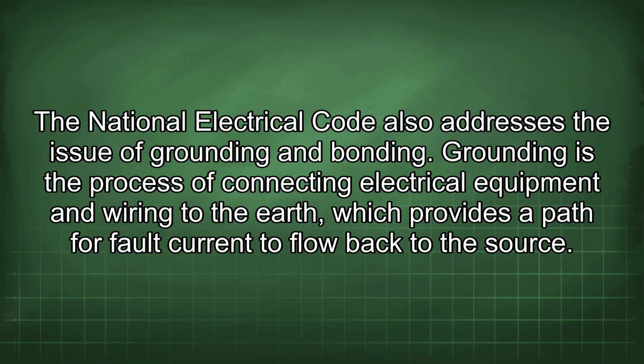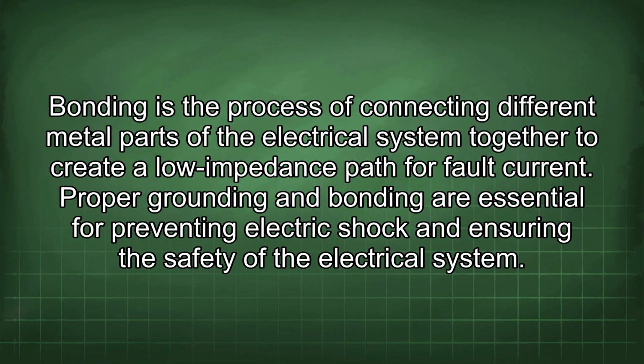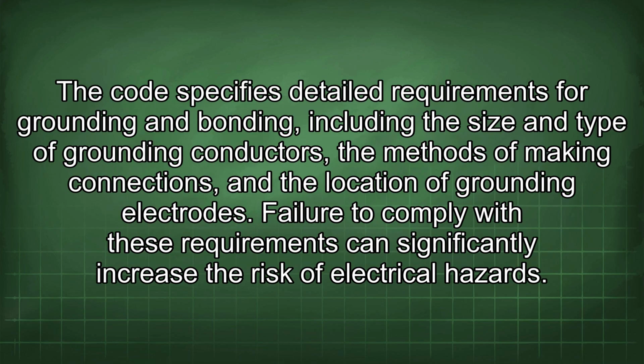The National Electrical Code also addresses the issue of grounding and bonding. Grounding is the process of connecting electrical equipment and wiring to the earth, which provides a path for fault current to flow back to the source. Bonding is the process of connecting different metal parts of the electrical system together to create a low impedance path for fault current. Proper grounding and bonding are essential for preventing electric shock and ensuring the safety of the electrical system. The code specifies detailed requirements for grounding and bonding, including the size and type of grounding conductors, the methods of making connections, and the location of grounding electrodes. Failure to comply with these requirements can significantly increase the risk of electrical hazards.